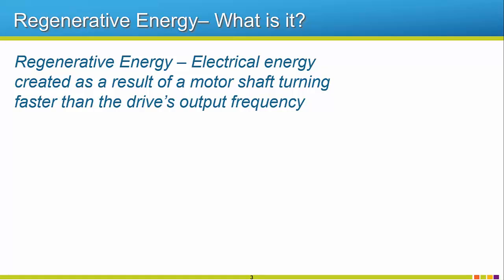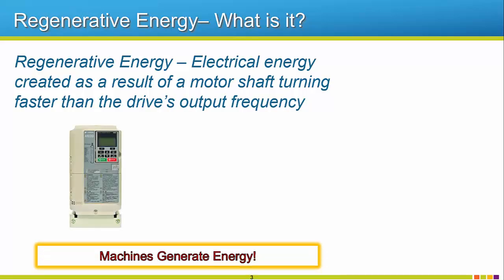To understand what the R1000 is and when it is practical to use, let's start with a brief lesson on Regenerative Energy, commonly called regen for short. Regenerative Energy is defined as the electrical energy created as a result of a motor shaft turning faster than the drive's output frequency. This is because an overhauled motor acts as a generator. Think of it this way: when a motor turns, it consumes energy, but when it is turned by something else, it generates energy.